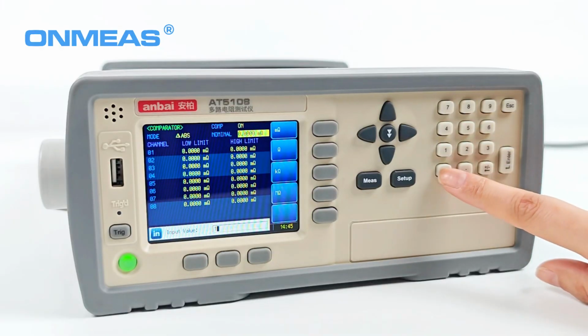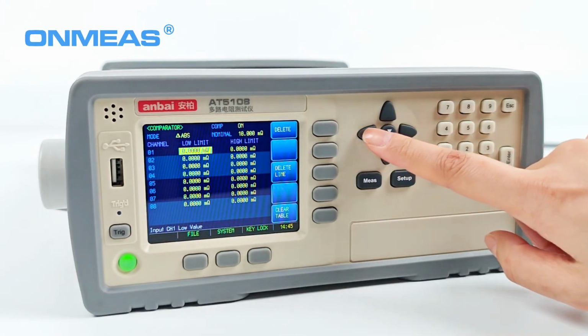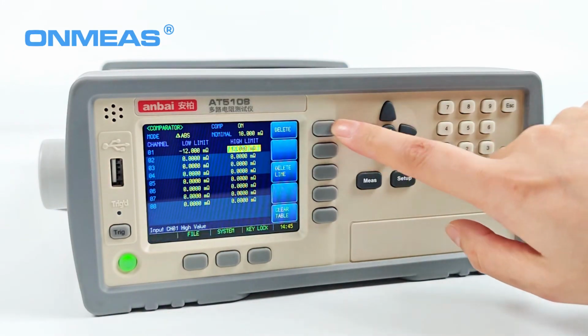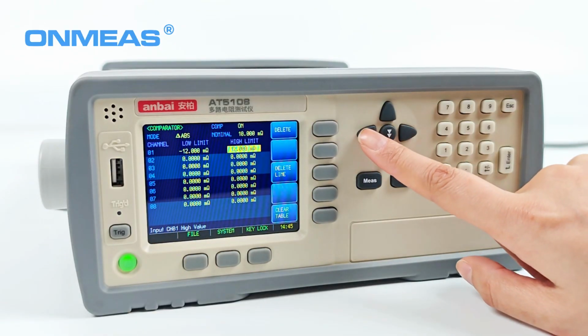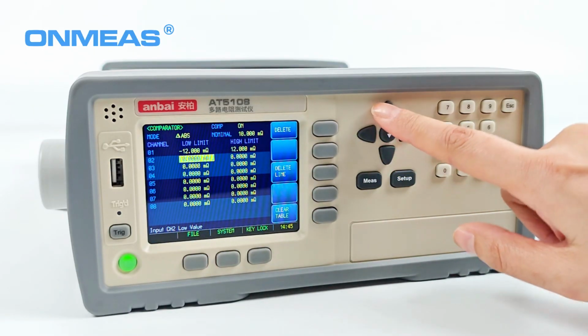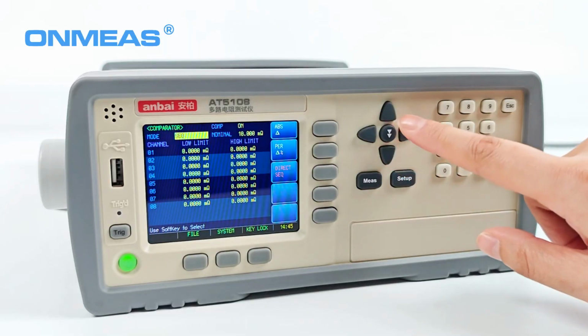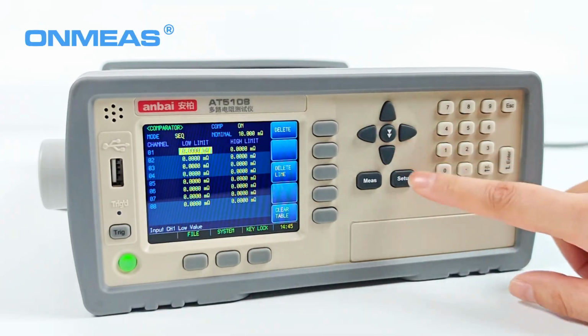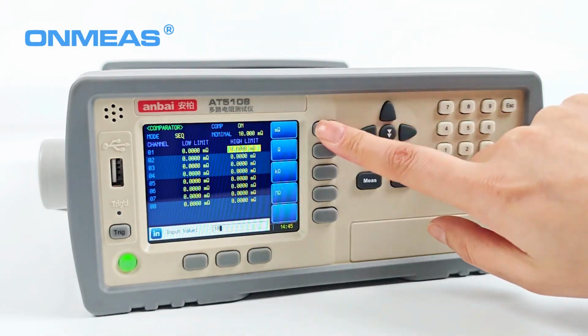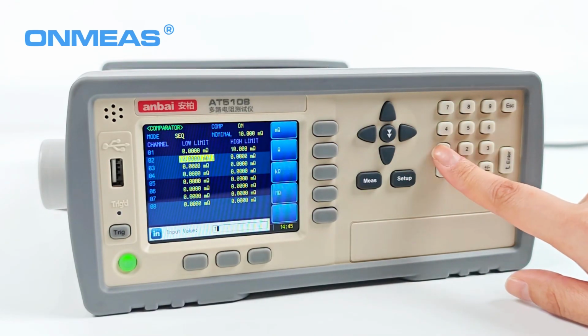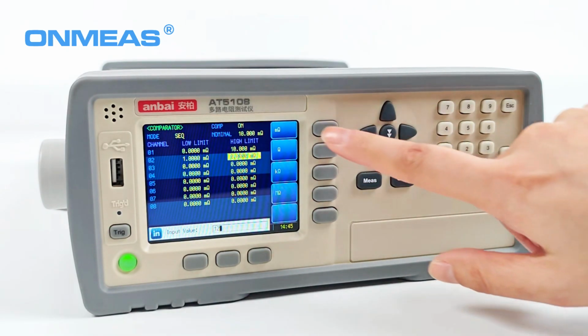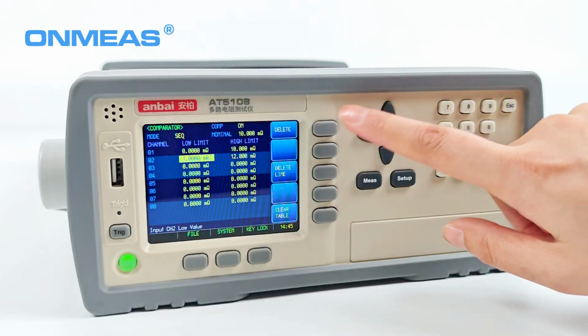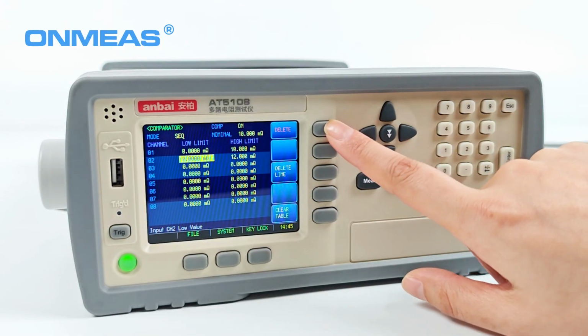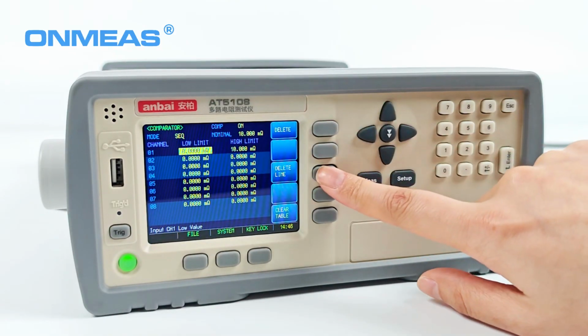The instrument has an internal handler interface for outputting the results to relays, PLCs or industrial computers. On the comparator page, you can set the following items: comparator switch and input mode for comparator gears, comparison method settings, nominal value settings, as well as the upper limit and lower limit data input for each gear. The upper and lower limit values can be deleted individually or in batches through the function keys.